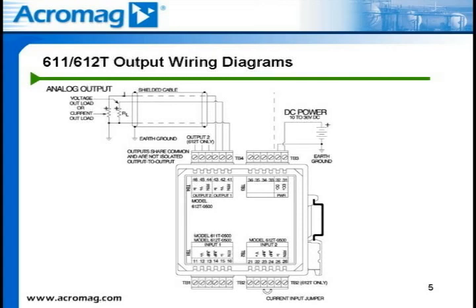The output connections for current output applications are simply the I+ terminal of the 611T or 612T transmitter to the positive side of the load, and the negative side of the load to the RTN or return terminal on the 611T or 612T isolated transmitter. And for voltage output applications, the positive side of the load connects to the V+ terminal, while the negative side of the load is tied to the RTN terminal on the 611T or 612T isolated transmitter.